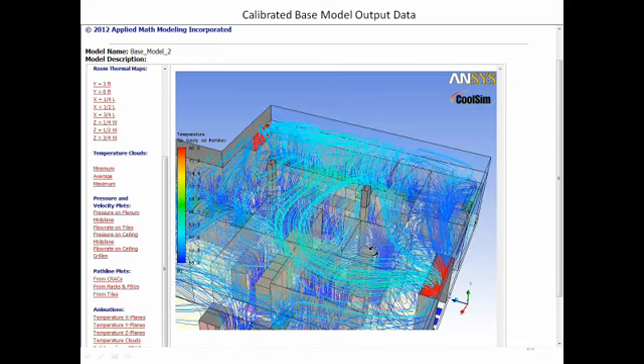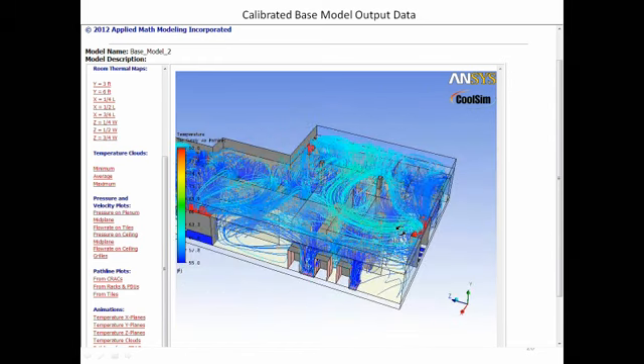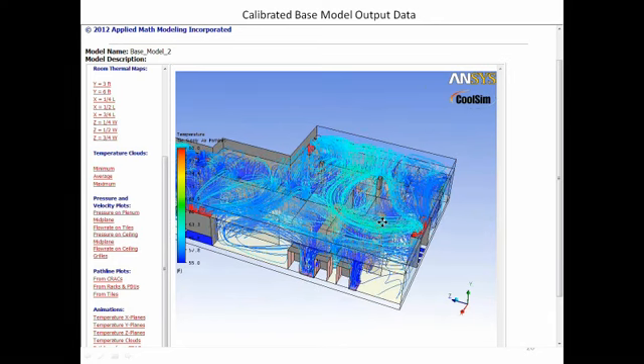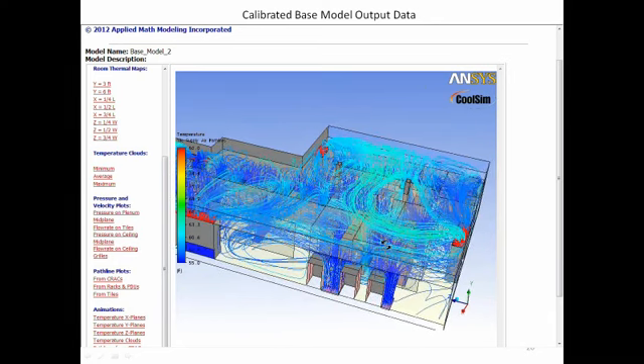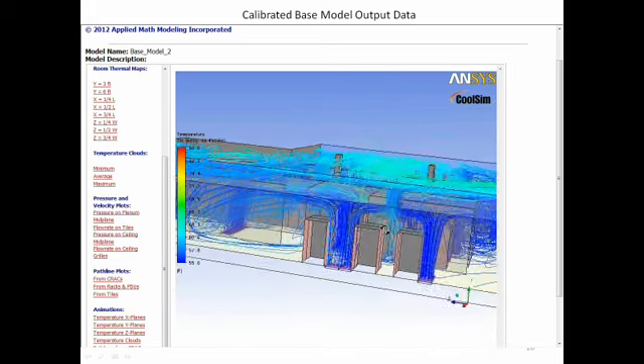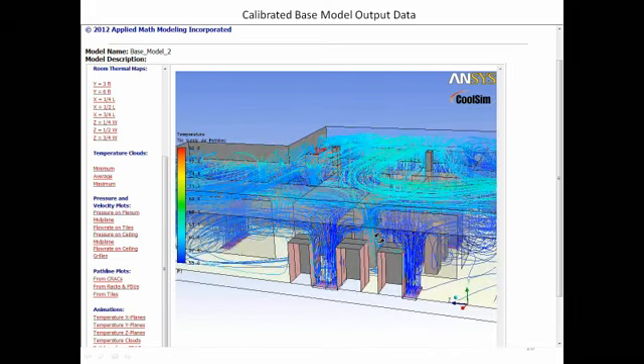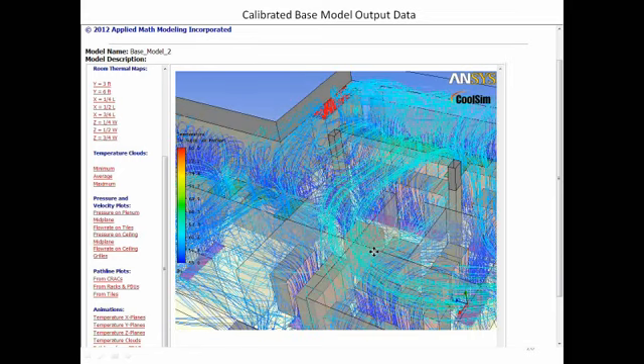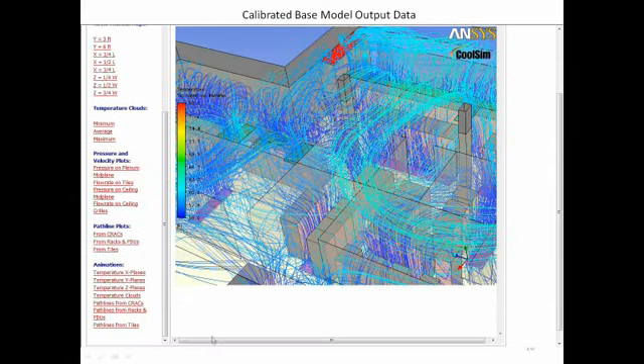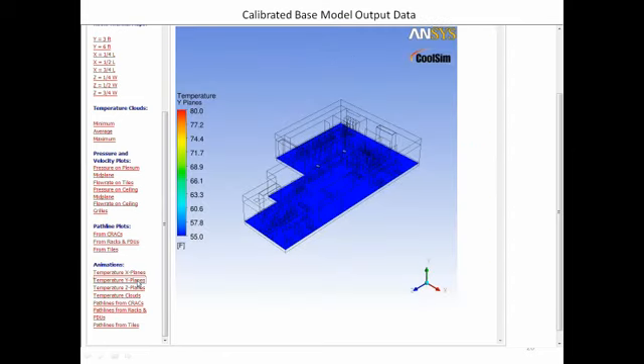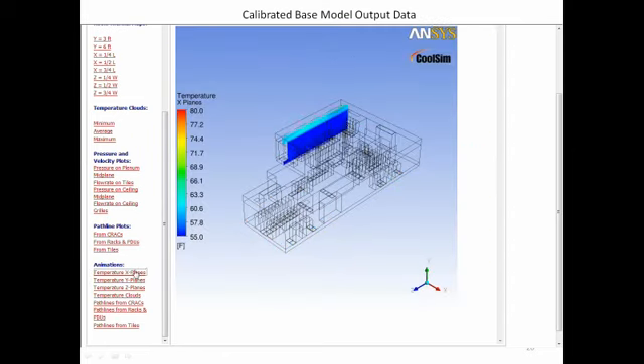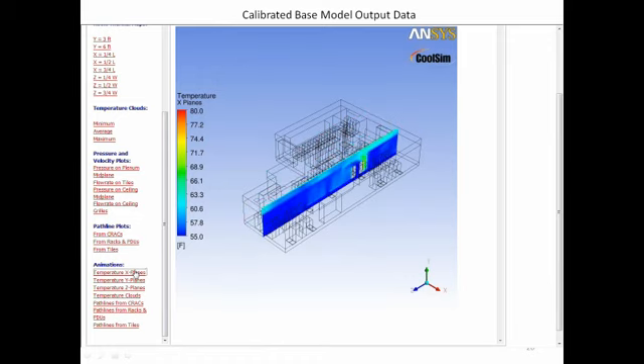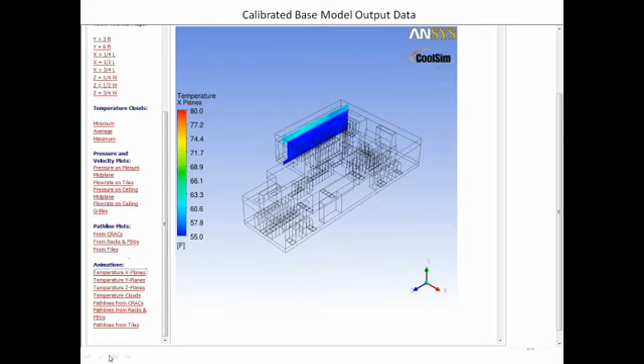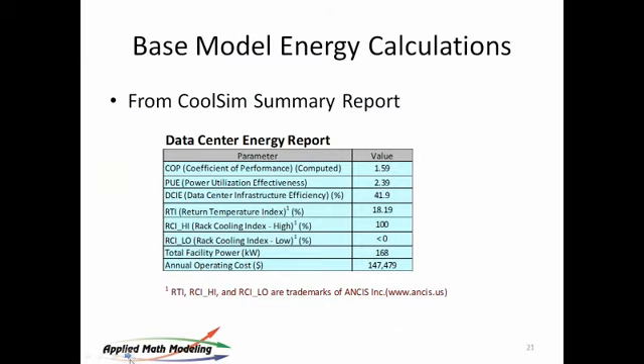This is also a good illustration to show a customer, if you're a colo provider, that the room is just way too cold, because customers will often push you to run them more inefficiently than you'd like, because they want to make sure their equipment is, quote, safe. We also have animation sequences here, and every time you do a CoolSim run, the same data comes back, the same set of plots, the same set of output. You do not have to push any buttons or turn any dials to get this to happen. It's a fully automated scripted sequence.